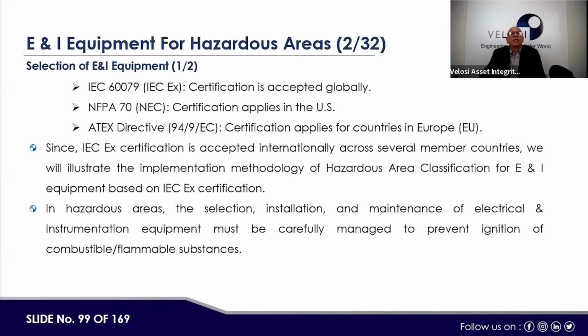If we say that IEC 60079 certification is accepted globally, this is one piece of information where people might be interested: IEC 60079 certification is accepted globally for the equipment, not for the people. Then NFPA 70 NEC certification applies in the US. And the ATEX directive certification applies for the countries in Europe.